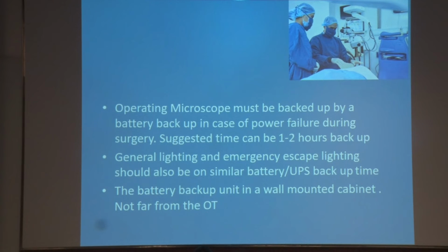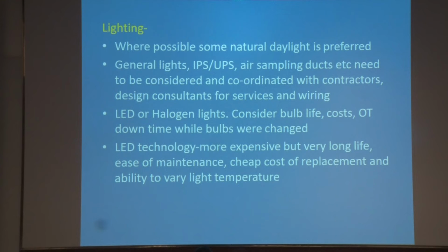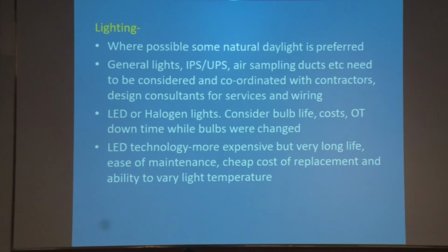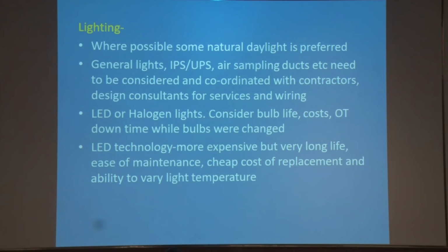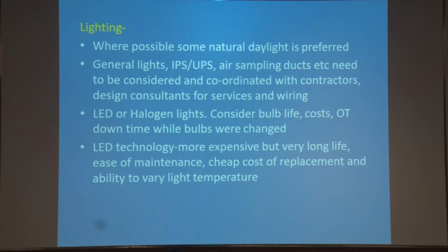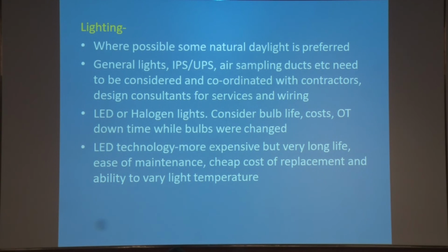The operating microscope should be backed up by a battery backup in case of power failure during surgery. The suggested time can be 1 to 2 hours, which is sufficient to even finish off most retinal operations as well. For lighting, nowadays LED lights are generally used, which are slightly expensive, but they are easy to maintain and they last for a very long time. There should be sufficient light, but the light should not be so much that it blinds you; it shouldn't hurt your eyes. So there should be sufficient light in the OT.